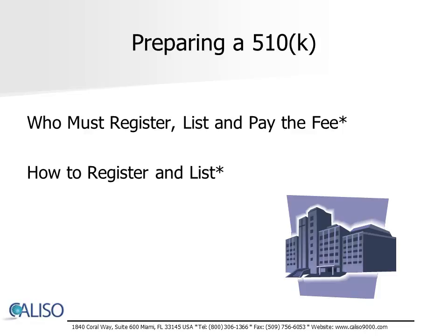The FDA has a very specific method to register and list your device. Please review the link How to Register and List for details. Registration information must be submitted each year between October 1st and December 31st, even if no changes have occurred. This is known as annual registration.